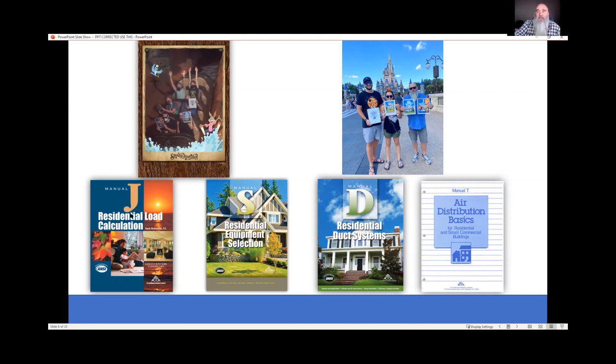But enough of that. Manual J is the book that does the loss and gain on residential structures. In my mind, it's very straightforward. I would like to think that for the average practitioner, that holds true also. Manual S is the book that, and I'm making this one up on the fly, it doesn't stand for shunned, but sometimes it seems like it is. And I almost want to say it's as important as any of, if not more important than any of the other books in the design series. It is a book that aids us in selecting proper equipment. A load calculation gives us a lot of information, but especially when we're talking about air conditioning, the numbers it produces need help, and Manual S aids us in that. It's going to tell us what our airflow is supposed to be.